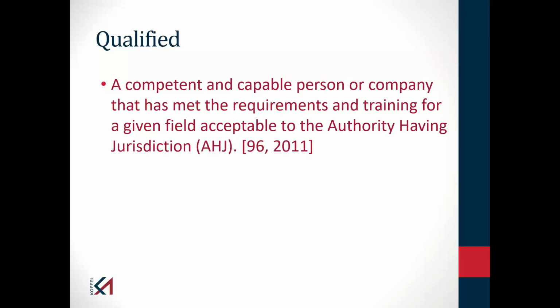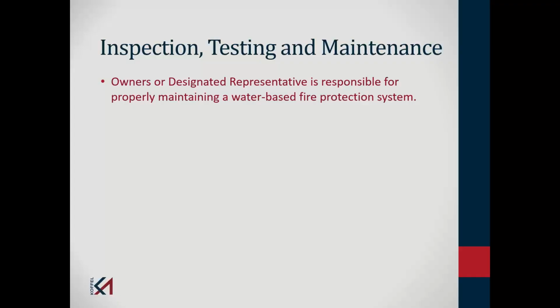The way I would enforce that is if somebody was doing their own inspection, test, and maintenance, I would potentially ask to see a certain test to be performed. And if I asked for an inspector's test and they went and did a main drain test, then I would probably say that person isn't qualified to do the test because they don't understand the difference between those two tests that are required by NFPA 25.